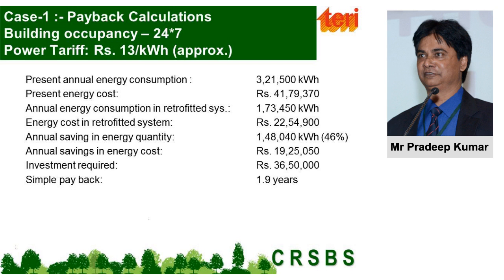So it is a 24 hours occupied building with the highest tariff, so about 2 years. Now, depending upon the tariff structure, this is going to increase. We found that if we are paying somewhere around 7 rupees and our occupancy is only daytime, 5 days in a week, then it's something around 8 years. This is something which we really have to look into very judiciously in the design system, even though the payback period is 8 years.